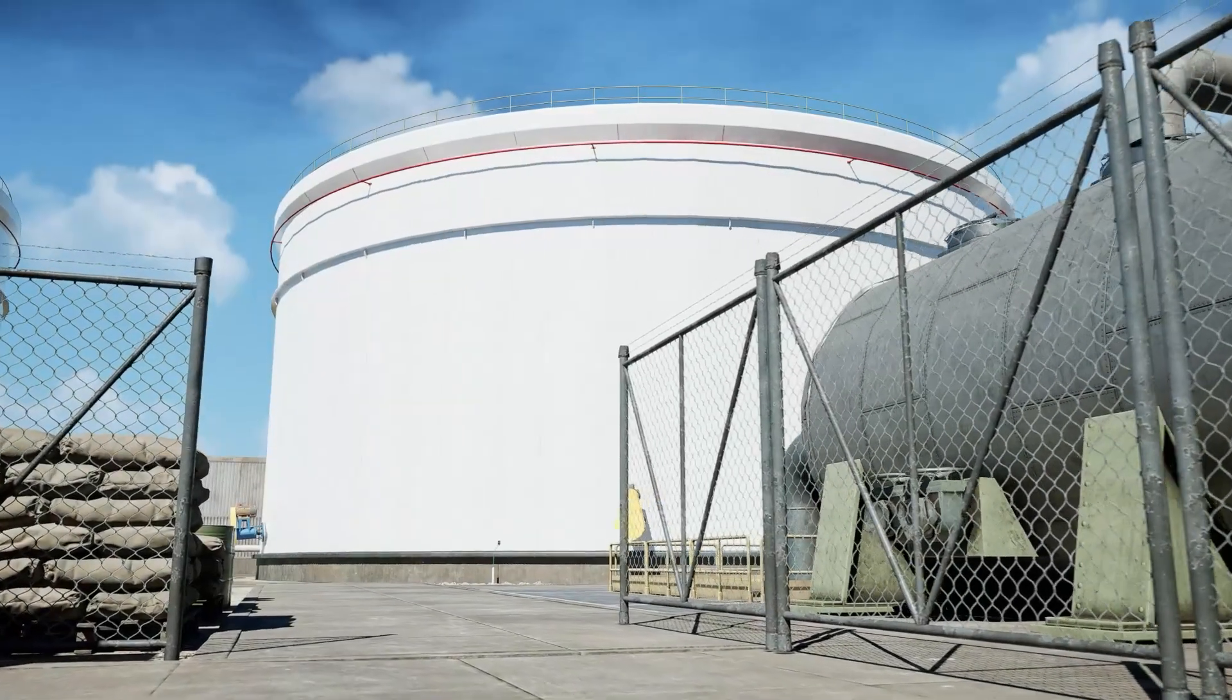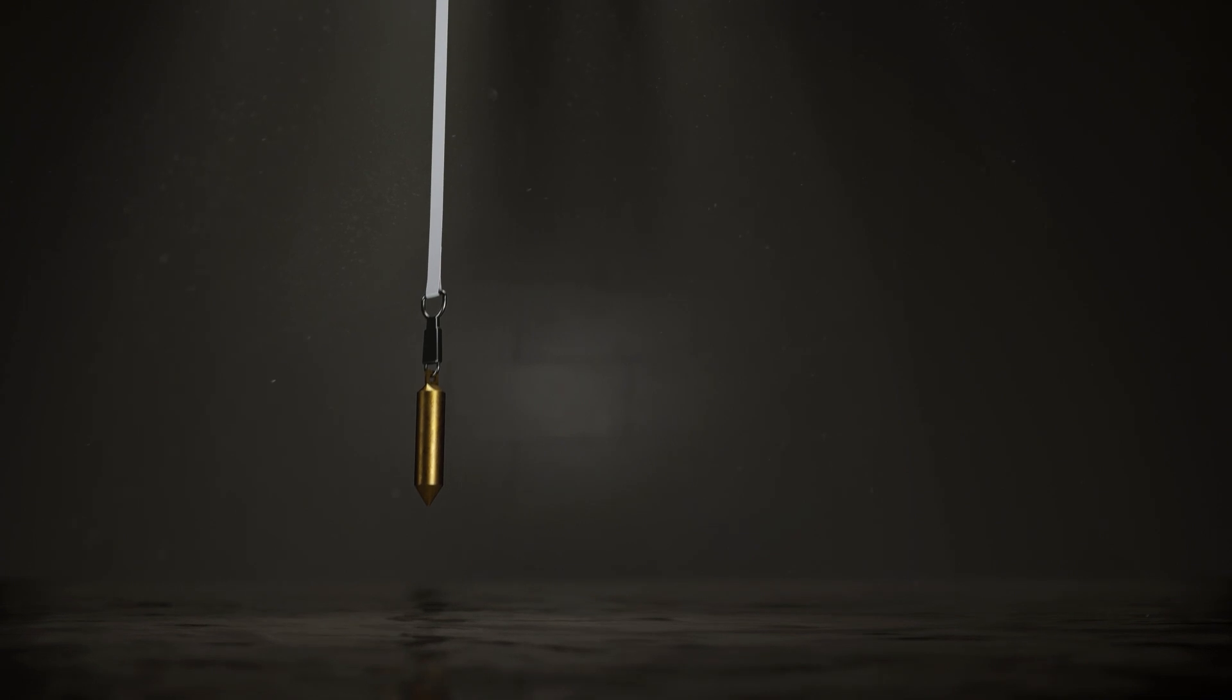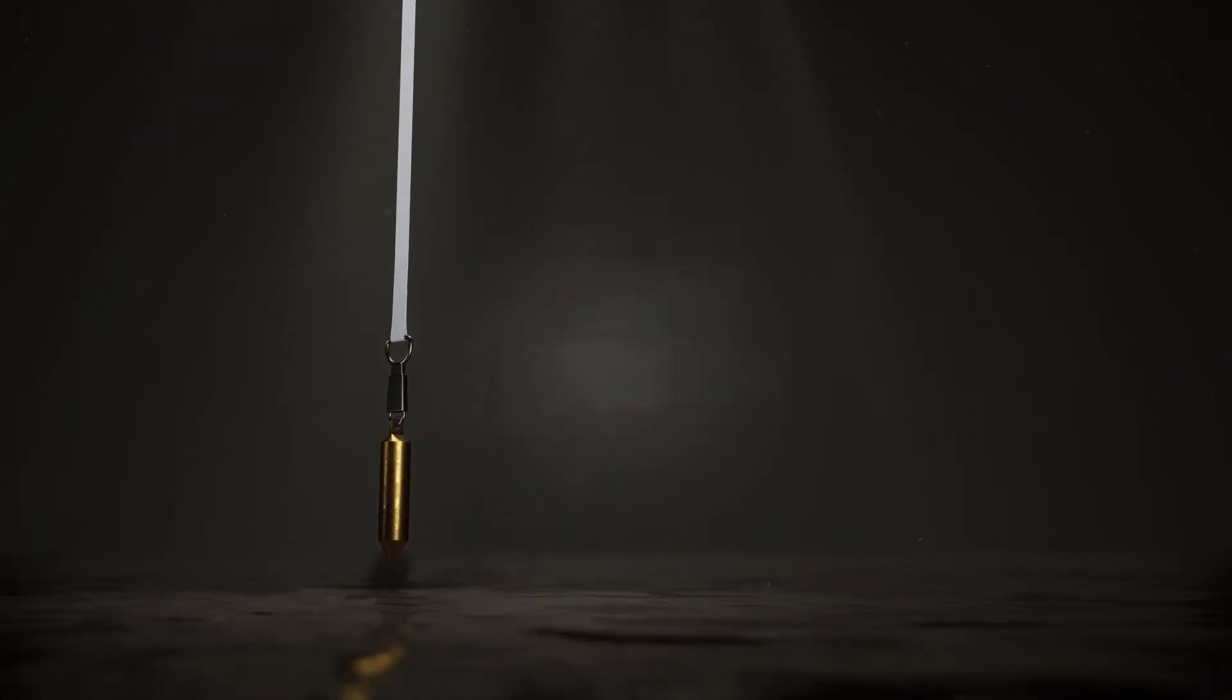Let's look at an example, in this case a conductive storage tank. If properly earthed, the charge on the outside of the tank will flow to earth. But a charge can exist in the tank for some considerable time following pumping or mixing. If a metal sampler or dip tape is brought close to the liquid surface, this charge will rapidly discharge, leading to a spark.